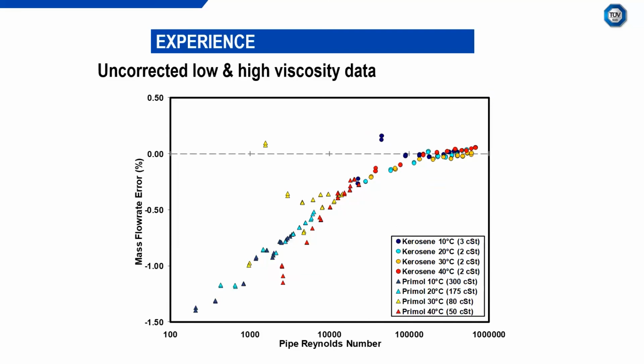So one of the main manufacturers, Endress and Hauser, now have a patented Reynolds number correction, and it takes into account these Reynolds number effects. So compensation is possible versus Reynolds number. There is a patented Reynolds number correction, or you could apply something similar in your flow computer, basically with a calibration curve. You just need to make sure you don't fall foul of the patent. So what do we recommend? Our recommendation would be to calibrate with respect to Reynolds number if you're operating with relatively high viscosity fluids.